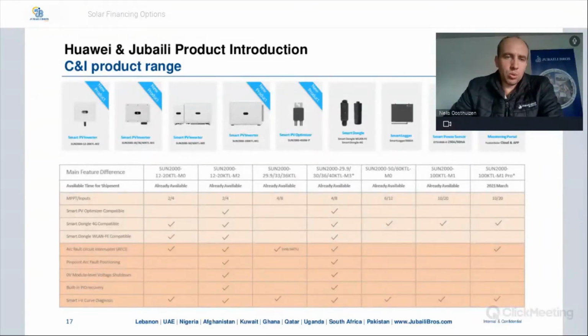The M2, which supports the optimizers, the arc fault interruption, the 0 volt module level shutdown. That's only available with the optimizer. The optimizer is what gives you the 0 volt module level voltage shutdown. Then all the newest range of inverters has got the built-in PID. So it would be the M2 on this entry level range.